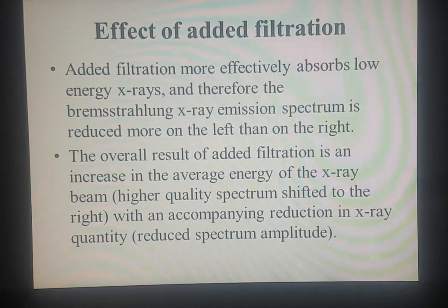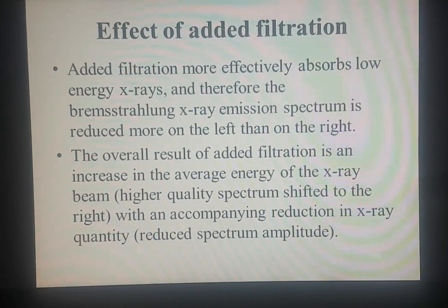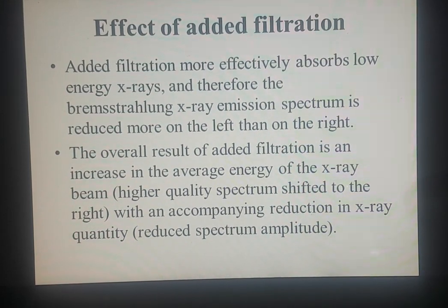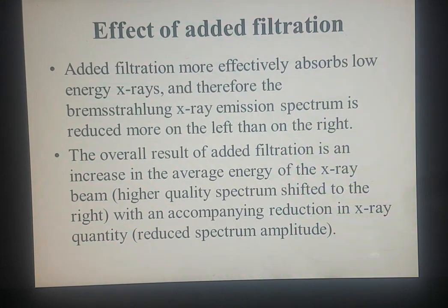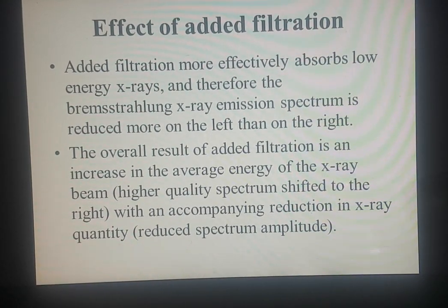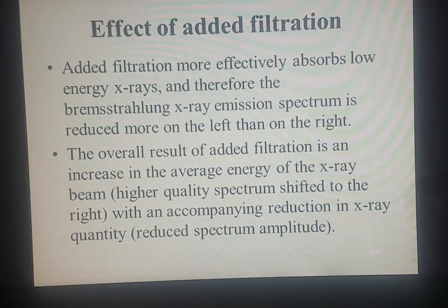The effect of added filtration is also very important, as we know that added filtration can effectively absorb the low energy X-rays. So what effect would it cause on the bremsstrahlung X-ray emission spectrum? It will definitely reduce the position of the X-ray spectrum on the left side as compared to the right side. There would be more high energy X-rays, so the shift would be towards the right, and as it has absorbed less energy X-rays, there will be reduced shift on the left side.